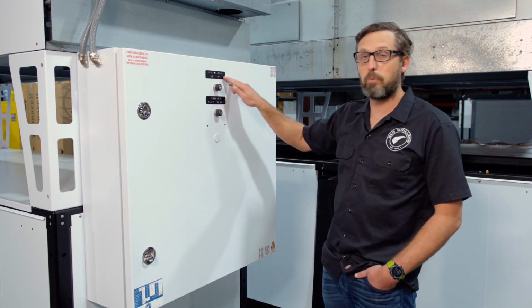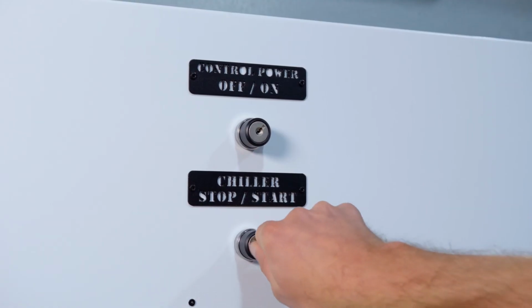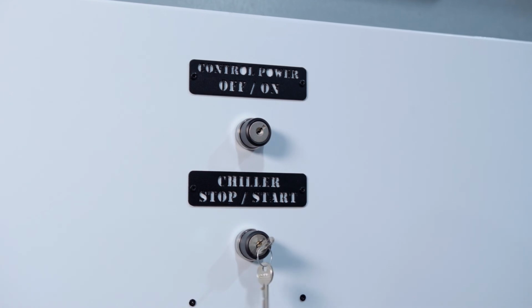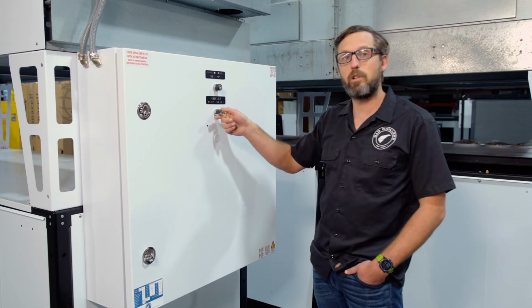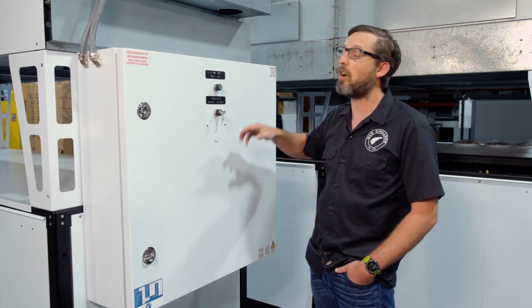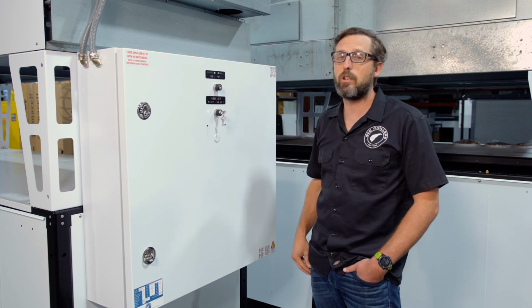We're going to take the key from the control power that we turned on earlier. We're going to put it in the chiller stop start, and we're going to turn that to on. Once we do that, you're going to hear compressors kick on, which will be followed shortly by the fans. That means that you're chilling.